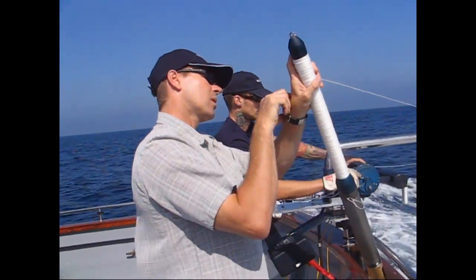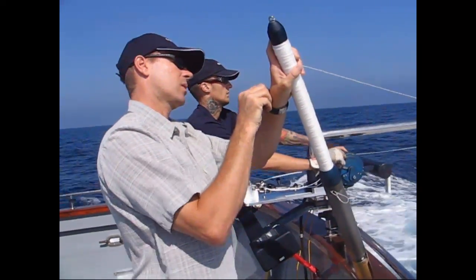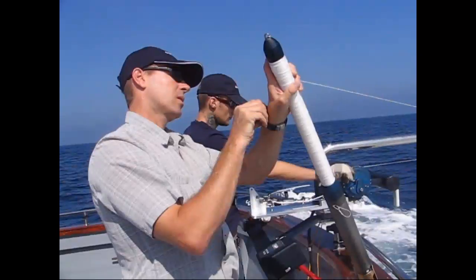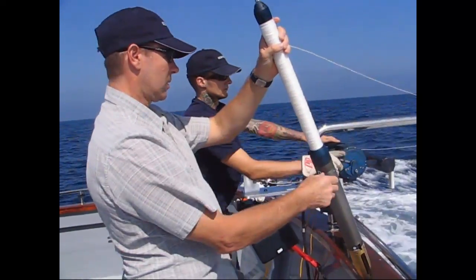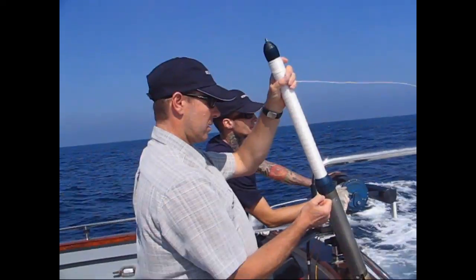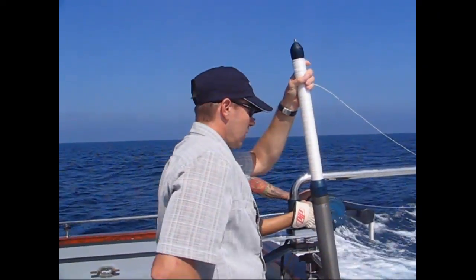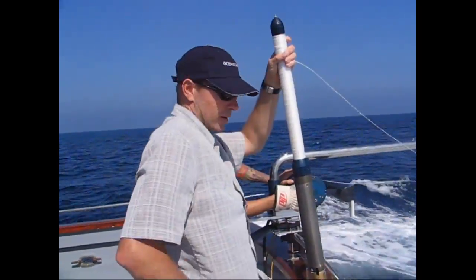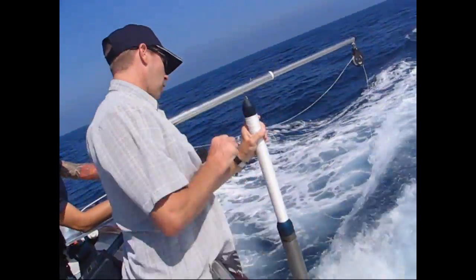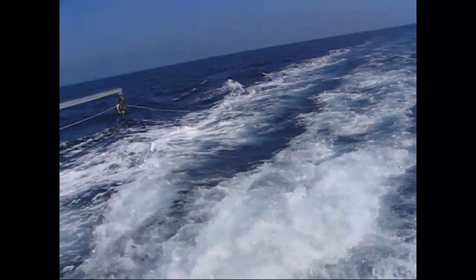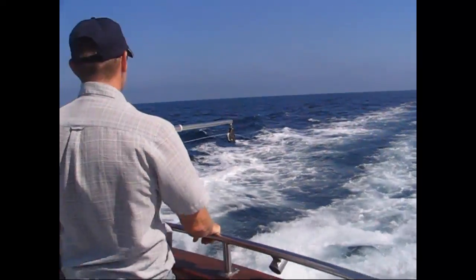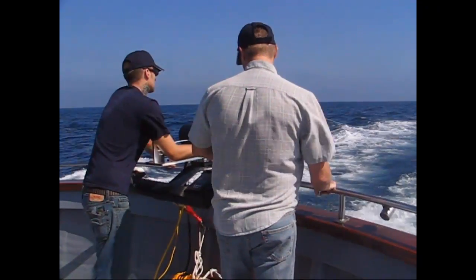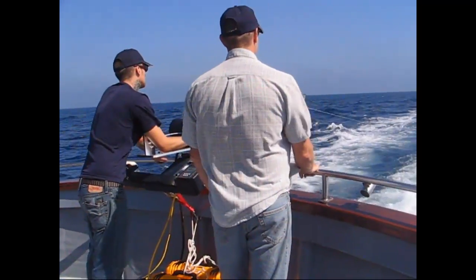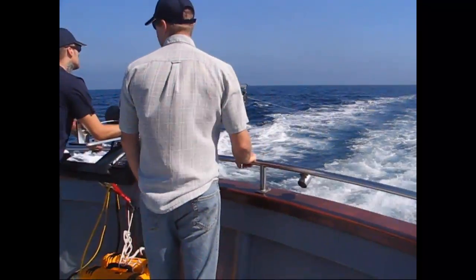This last deployment video shows the CTD probe being deployed using the Series 1 winch system. So the magnetic plug is pulled to start the probe logging. The probe is going to be dropped gently into the water right behind the ship, that's really hardly moving relative to the vessel there. You get a good indication of the relative velocity. You'll see the line as it's paying out. Again, not too much tension on the line there. Get quite a nice indication of how the line pays off the winch. It's really only being pulled off the winch there by the movement of the ship.